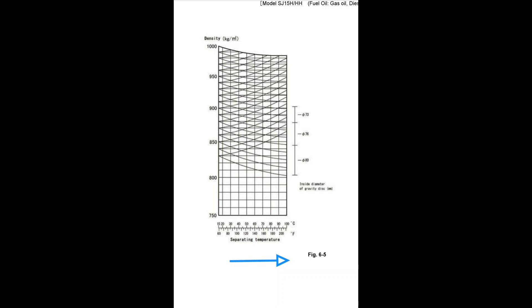Here you can see how a nomogram looks like. This is for the model SJ15H of the Mitsubishi purifier. We should know what parameters are given on the nomogram chart. You can see the separating temperature in degree centigrade and degree Fahrenheit on the x-axis. Also you can see the density or specific gravity for this particular model going from 750 kg per meter cube to 1000 kg per meter cube. On the right side, you can see the inside diameter of the gravity disk in mm. Please note it is the inside diameter and not the outside diameter.